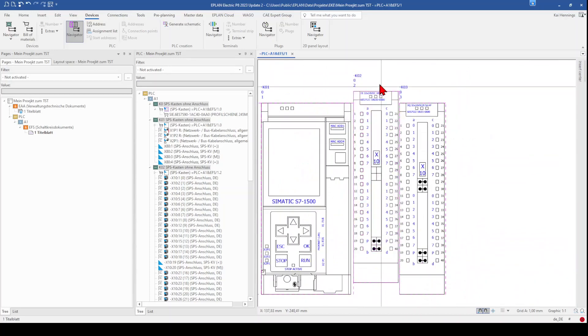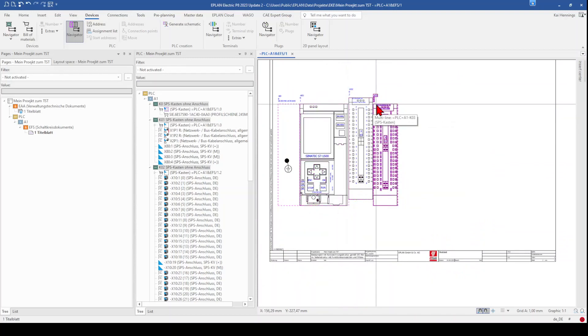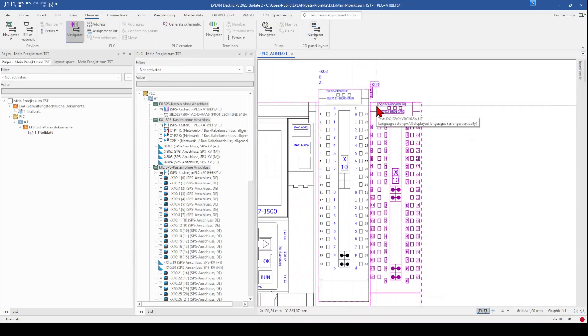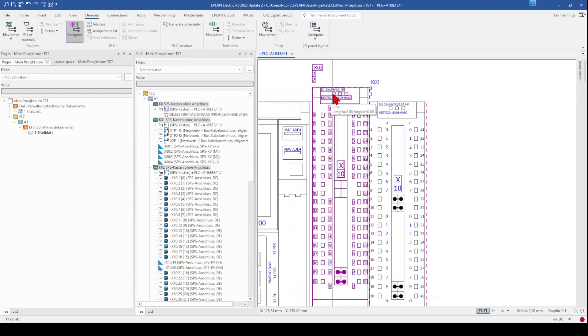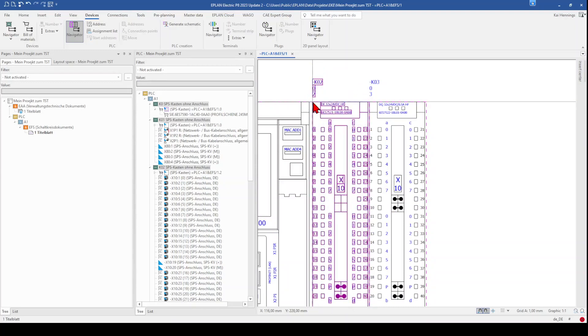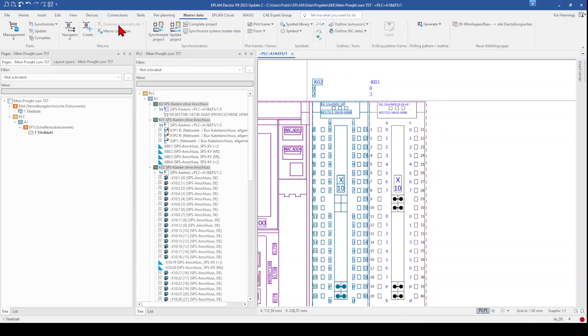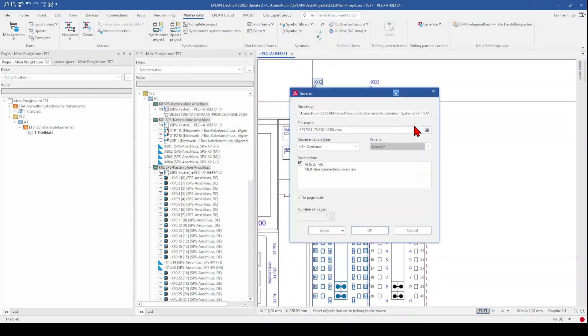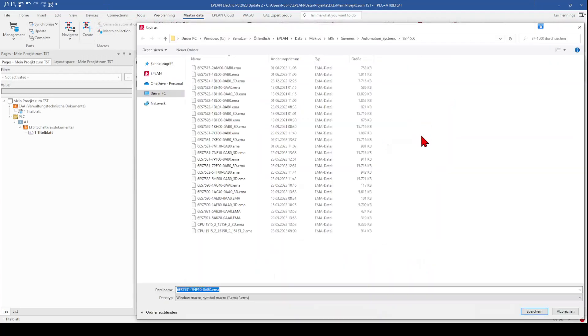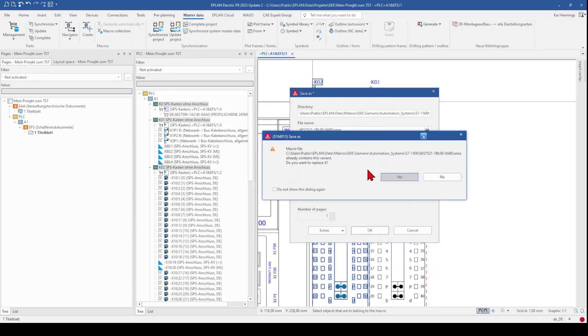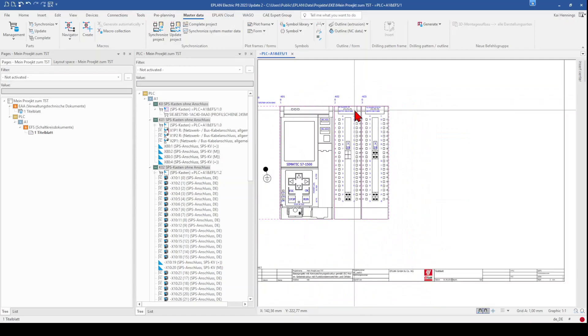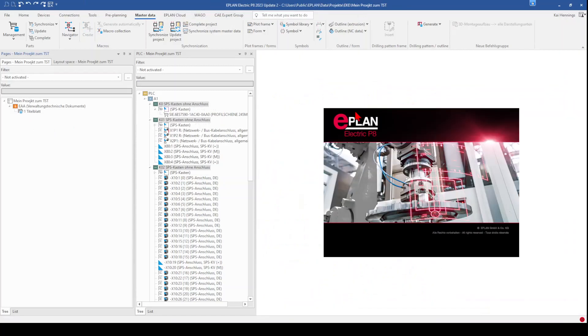So what happened here? Why is this not in line with the other ones? ePlan places your macros directly on the same position like you have created the macro. So what we need to do is that we need to upgrade this macro. So we shift this here to this position, right position. And then we can go to master data, create. And we select our macro here. And now it's important that you select the representation type overview and the variant E. This is the requirement to get this function. So we click OK and we want to replace it. And now we can make undo. So now the project is empty again.